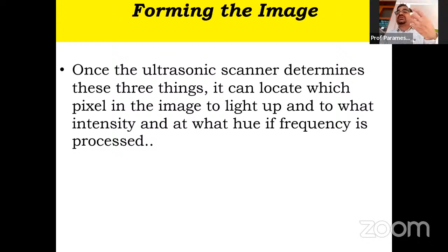Forming an image, that is, transforming the received signal into a digital image, may be explained by using a blank spreadsheet as an analogy. We imagine our transducer is a long flat transducer. At the top of the sheet, we send the pulses down the columns of our spreadsheet: A, B, C. We listen at each column for any returning echoes. When we hear an echo, we note how long it took to return. The longer the wait, the deeper the row. The strength of the echo determines the brightness setting: white for a strong echo, black for a weak echo, and varying shades of gray in between. When all echoes are recorded on the sheet, we have a grayscale image.